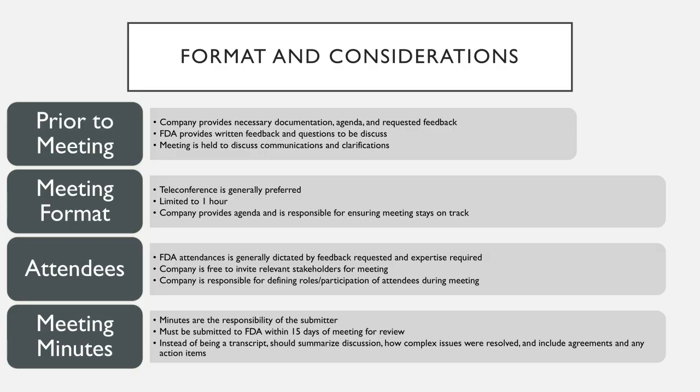Now, the format of the pre-submission process generally takes the form of a teleconference. This has been the main preference of the FDA, particularly since the rise of Zoom and Microsoft Teams from the COVID pandemic, and is a lot more convenient than any in-person meetings, which used to be actually quite common in prior years. They're limited to 1 hour, and the company has to provide the agenda and is responsible for assuring that the meeting stays on the allotted time scale.